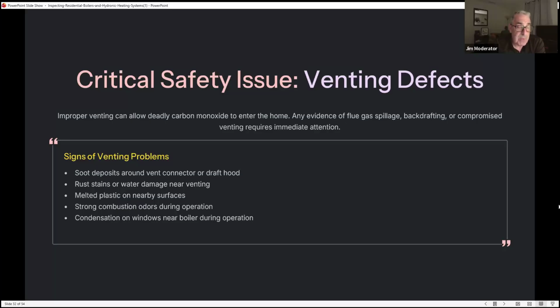Signs of venting problems: soot deposits around vent connectors or draft hood, rust stains or water damage near venting, melted plastic on nearby surfaces, strong combustion odors during operation, and condensation on windows near the boiler during operation.